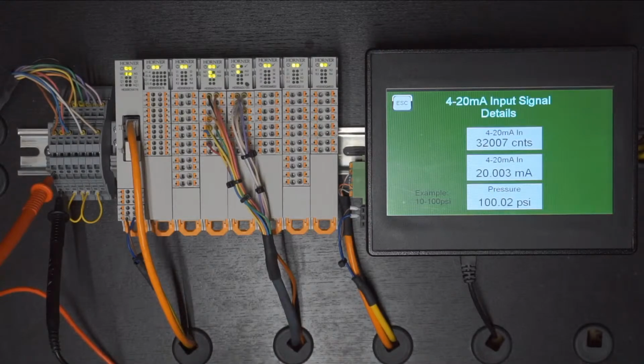Now, the time it takes them to respond, remember, is all influenced by the filter setting that we set up in configuration. The lower that filter number, the faster it responds. But again, we're also trading off on signal stability.